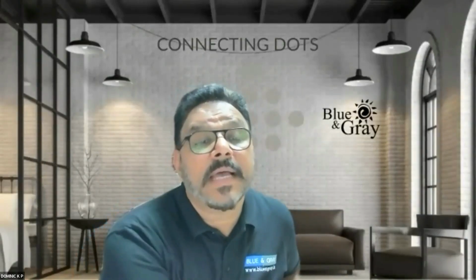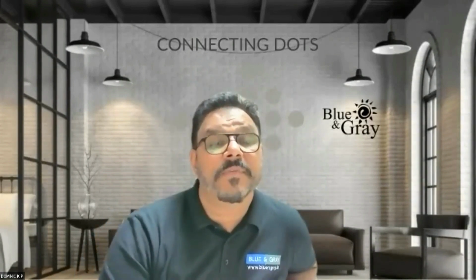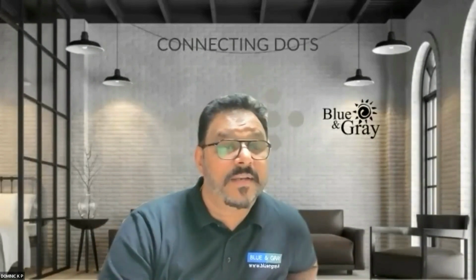Okay, though it is not related to today's subject, Hari Katla is asking, sir, I'm working in a fire and combustion research center. Some of the research equipment is giving a little bit of shock. For earthing, what type of earthing mixture will be used? So he's asking for one suggestion, one doubt. My God, your shock has nothing to do with the earth pit. If your shock has something to do with faulty equipment, the insulation must have gone. You should check the insulation resistance of the equipment, and if needed, you have to repair it. Hope Hari Katla, you got the message. Please check the equipment, not the earth.